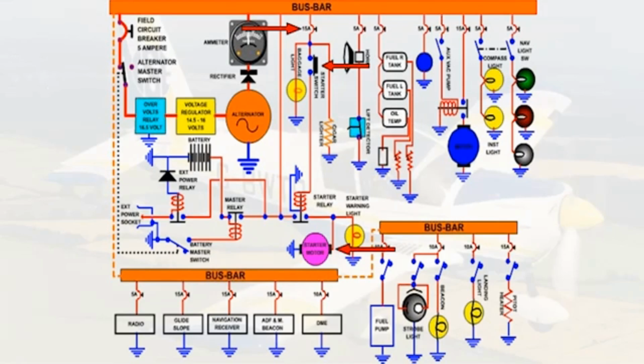A starter motor will take considerably more than 15 amps when it's first selected upon engine start. In fact, the initial load on the battery will exceed this figure by more than a factor of 4. That sort of current flow would cause the circuit breaker to pop open in an instant, and if it was flowing through the starter switch, it would either melt its contacts or weld them together, neither prospect being particularly appealing. To prevent either of these occurrences, the starting current is taken from the battery and passed through a starter relay.